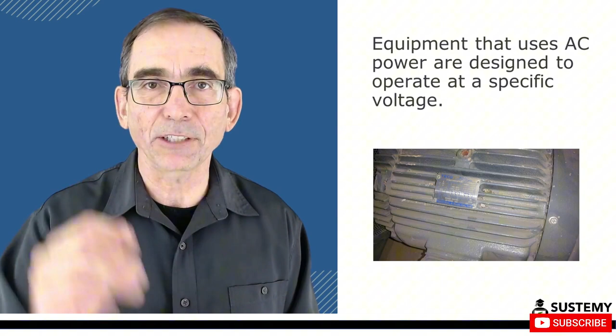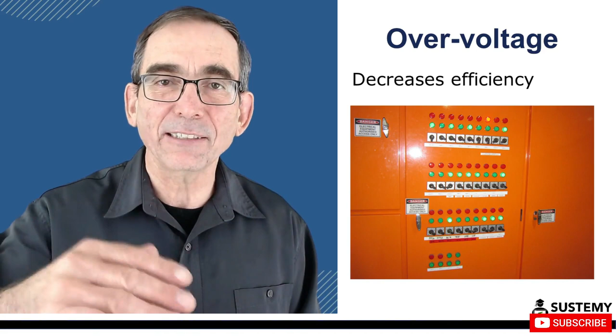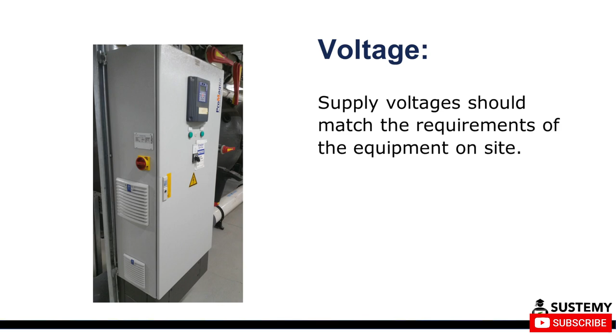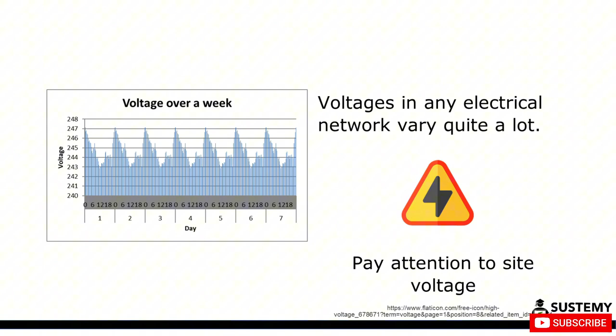It is also the case with high-intensity discharge lighting, including fluorescent lighting. The link in the resources section shows the impact of varying voltage on three-phase motors and how high-efficiency motors respond in a different way to low-efficiency motors. As over-voltage decreases efficiency, there is a strong argument for ensuring that supply voltages match the requirements of the equipment on site. Voltages in any electrical network vary quite a lot.